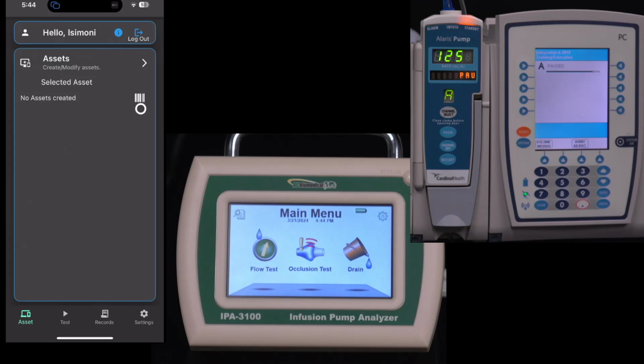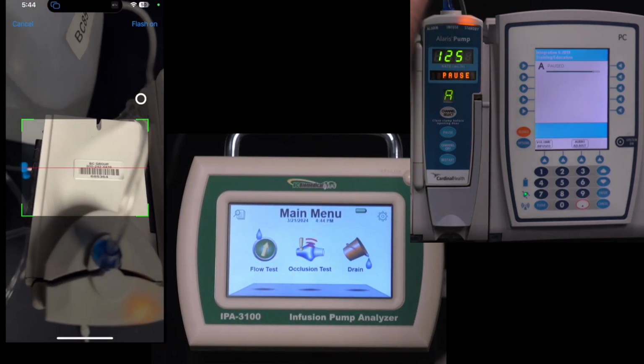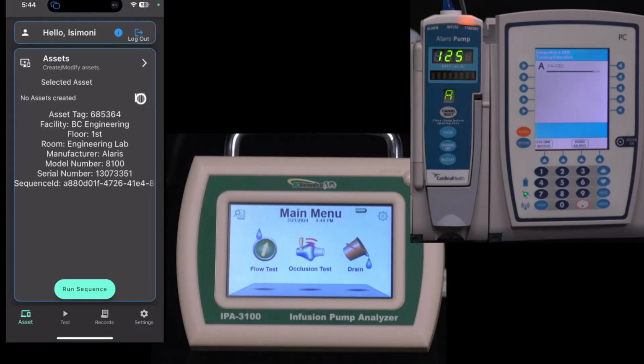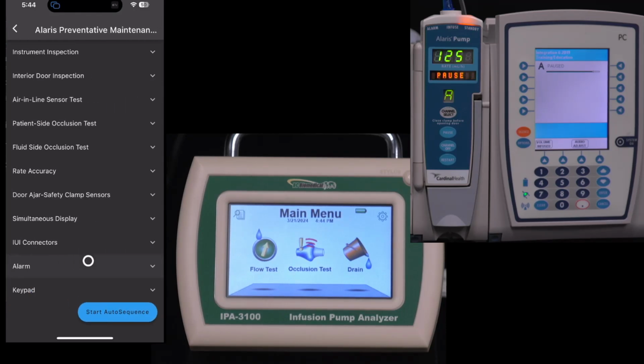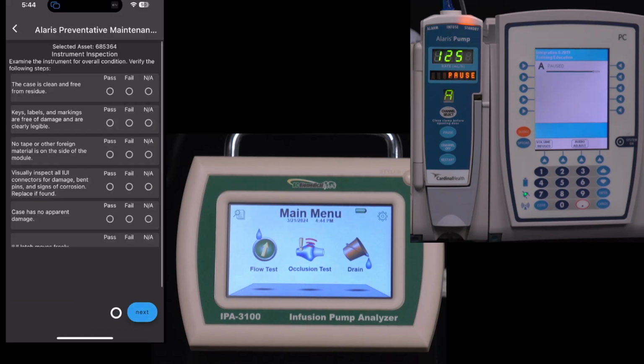So what I'm going to do is click right in here on the barcode, and that's going to open up my camera, and that's going to allow me to scan an asset tag. So I just happen to put one on that Alaris pump, and now we have that asset selected. It's all the information that I have pre-configured for that device in my database. It's ready to go. So it tells me, let's run our sequence. So we select that. Now this is going to show me a preview of the sequence that I'm running just to make sure, does this look like the right test that I want? And then we can hit start at the bottom.